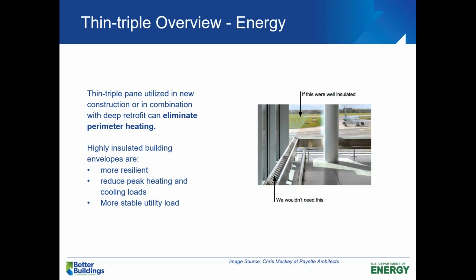The incremental cost of the triple pane or thin triple technology is much less than it costs to install perimeter heating. So if your building is planning HVAC improvements or a retrofit in the next several years, upgrading your facade or glazing now to this level of performance will enable you to potentially reduce your HVAC sizing and eliminate perimeter heating when you do that future retrofit.